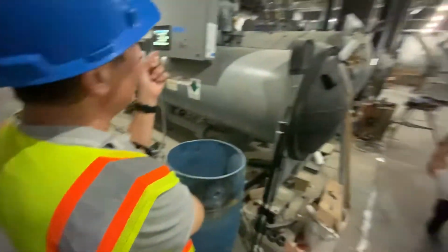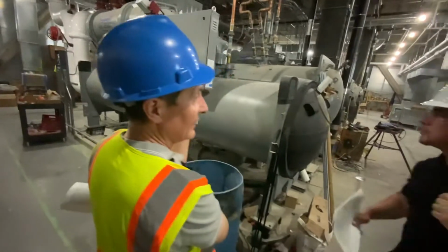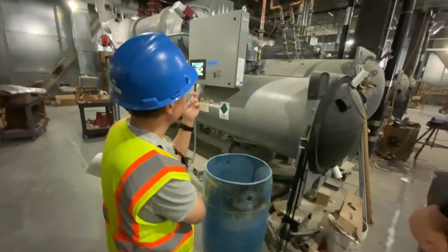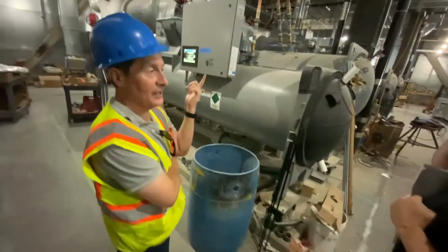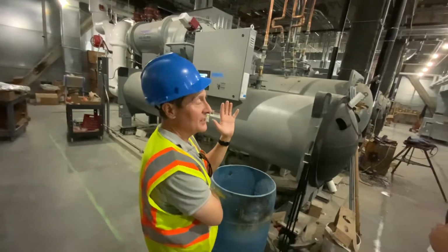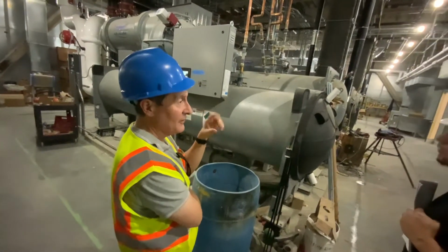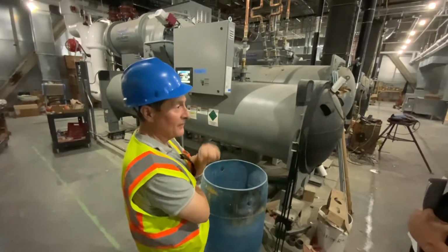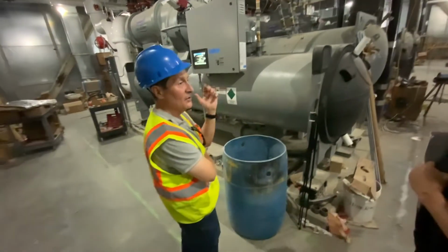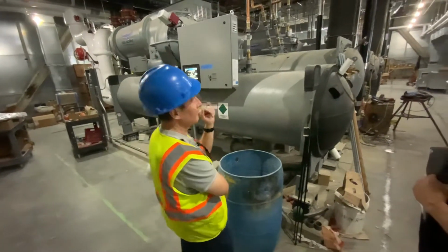Your relief valves should be checked periodically. When I say periodically, 3-4 years maybe or so, because if they ever do relieve, industry practice is to have them replaced. Even though they're back seating and they will prevent the charge from being lost, once they release the first time, it's a good idea to replace them.